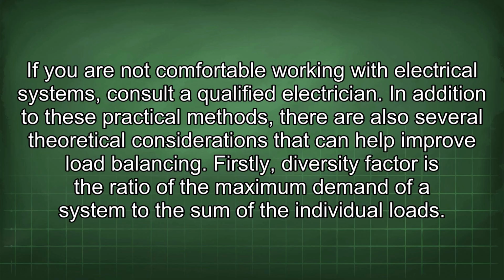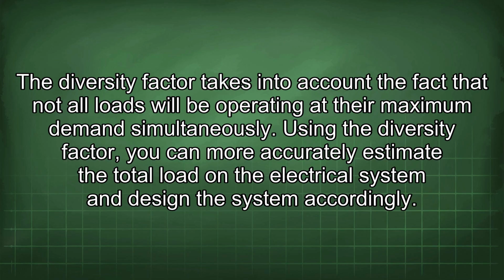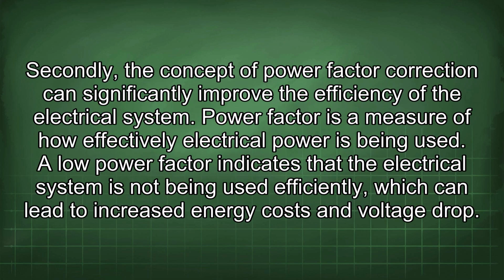Firstly, diversity factor is the ratio of the maximum demand of a system to the sum of the individual loads. The diversity factor takes into account the fact that not all loads will be operating at their maximum demand simultaneously. Using the diversity factor, you can more accurately estimate the total load in the electrical system and design the system accordingly. Secondly, the concept of power factor correction can significantly improve the efficiency of the electrical system.